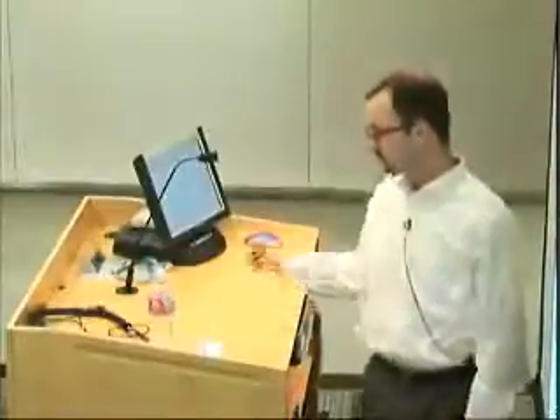So you control the fan speed. Yep. And then you manually set the set point of the chilled water or the air return temperature? What do you mean the set point? Right. So each implementation is slightly different. In this particular one, they were Liebert VFDs, so they have this retrofit kit. So we were sending commands to the Liebert units through their SiteLink Gateway protocol, which were resetting the set points, so basically for return air, because they were controlling off return air.